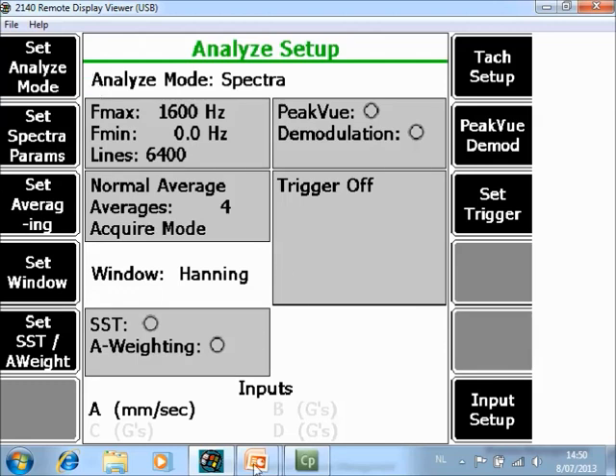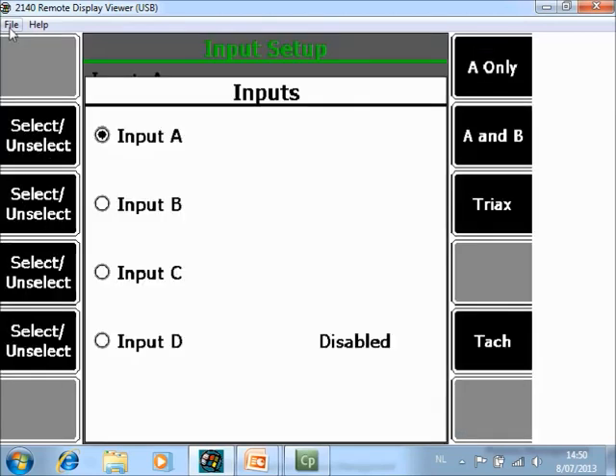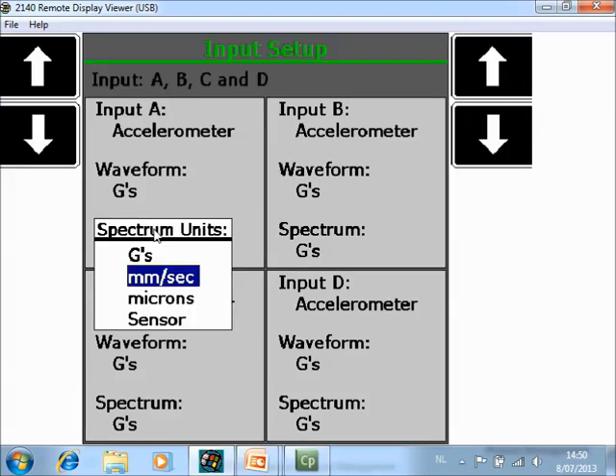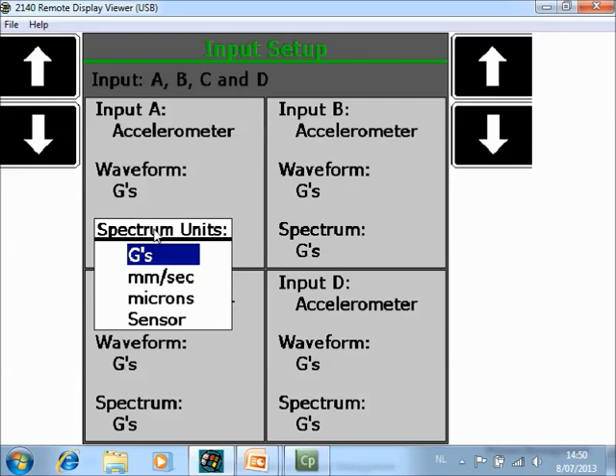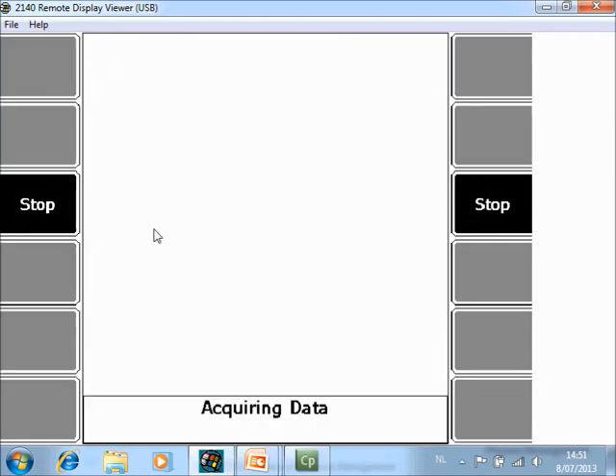Here, if you want, you can activate more channels using F12. I will also enable channel B, C, and D. I am working with accelerometers on all channels, and I want to see the spectrum in G's, so I change the unit to G's. When you press enter, it will collect data on 4 channels simultaneously with 6400 lines of resolution.